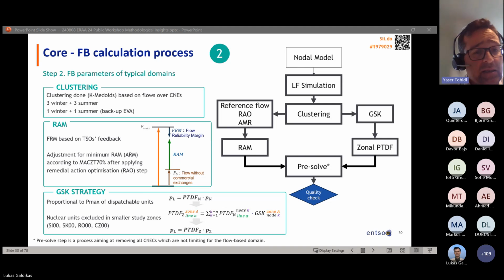On top of that, we do remedial actions to increase the minimum relative RAM, then apply an adjustment step on the final RAM to make sure all our RAMs are more than 70% of the capacity of the line. If not, we add a margin to the RAM called RAM adjustment.